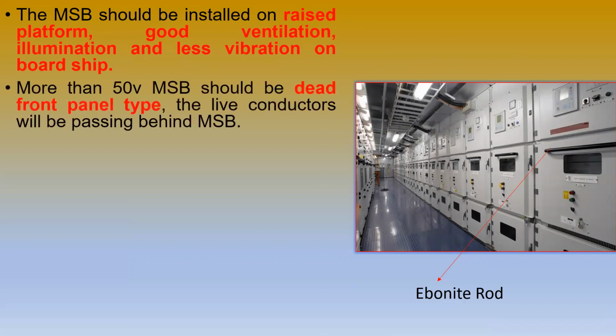So we have dead front panel type. For more than 50 volt, we use dead front panel type. The meaning is all the live conductors will be passing behind the MSB. Only the meters, instrumentation meters, indicators, synchronization indicating lamp, frequency meter, voltmeter, ammeter will be present in the panel board. All the live conductors will be passing behind the MSB. So this is the most important safety.